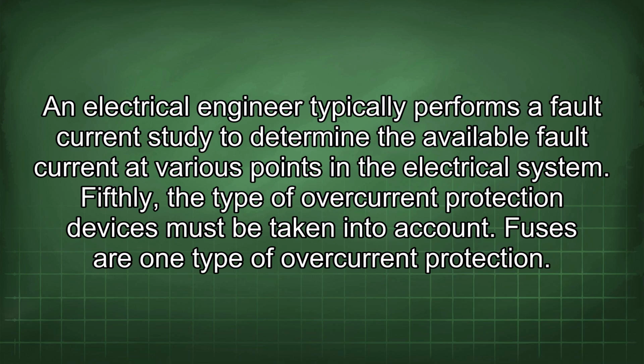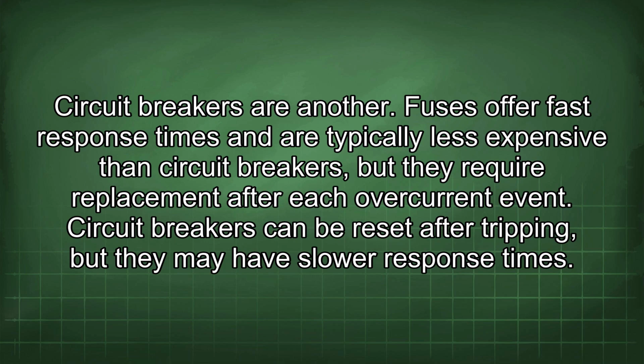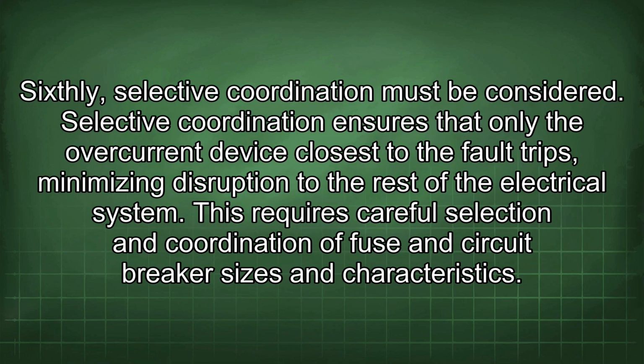Fifthly, the type of overcurrent protection devices must be taken into account. Fuses are one type of overcurrent protection. Circuit breakers are another. Fuses offer fast response times and are typically less expensive than circuit breakers, but they require replacement after each overcurrent event. Circuit breakers can be reset after tripping, but they may have slower response times. Sixthly, selective coordination must be considered. Selective coordination ensures that only the overcurrent device closest to the fault trips, minimizing disruption to the rest of the electrical system. This requires careful selection and coordination of fuse and circuit breaker sizes and characteristics.